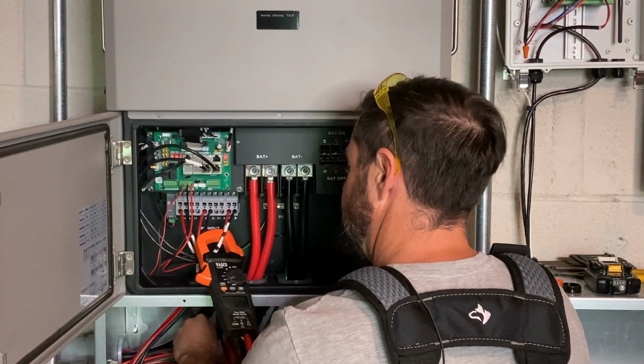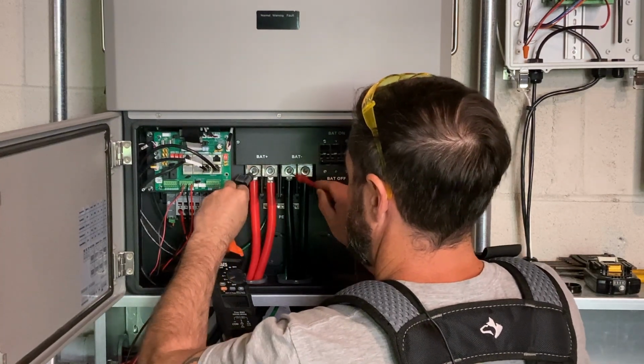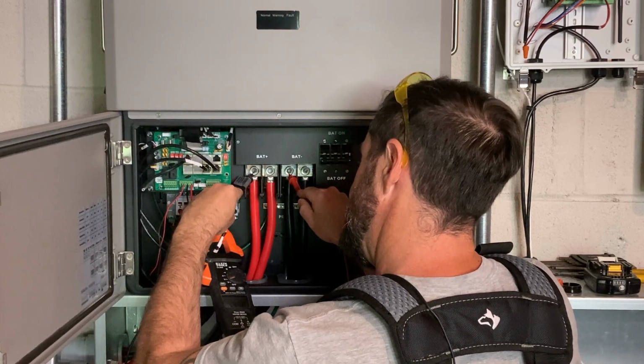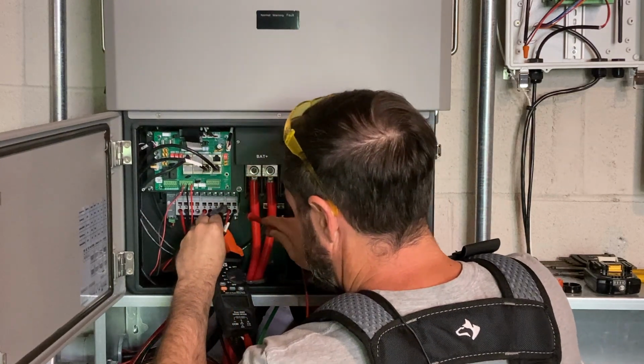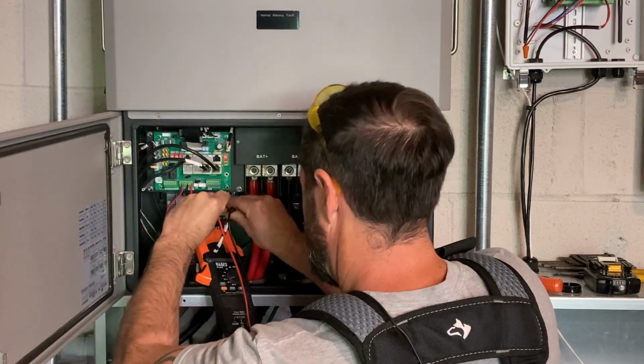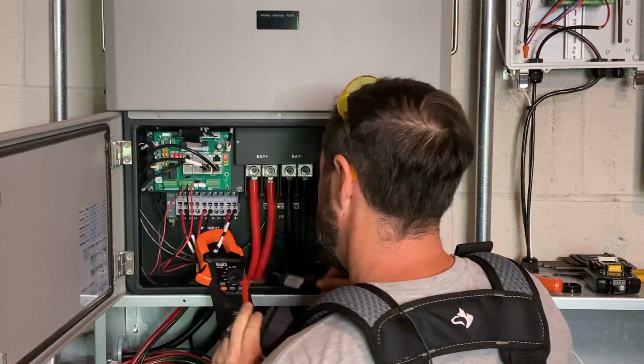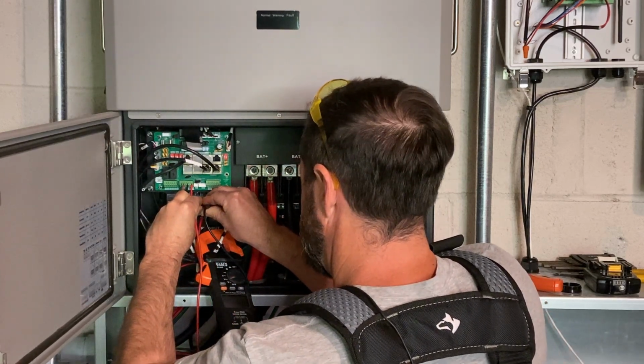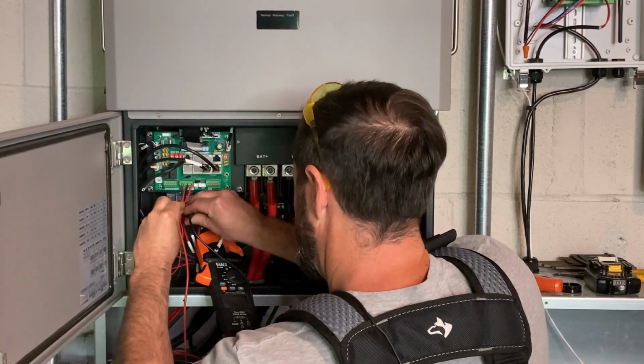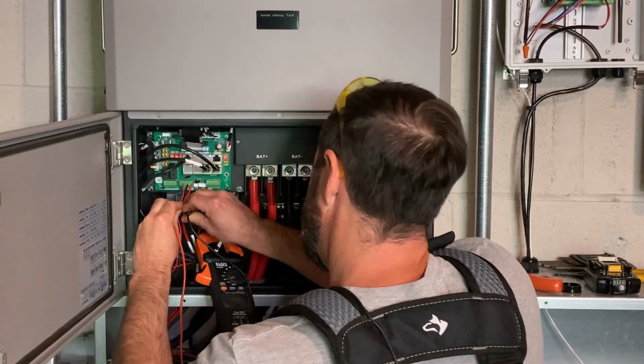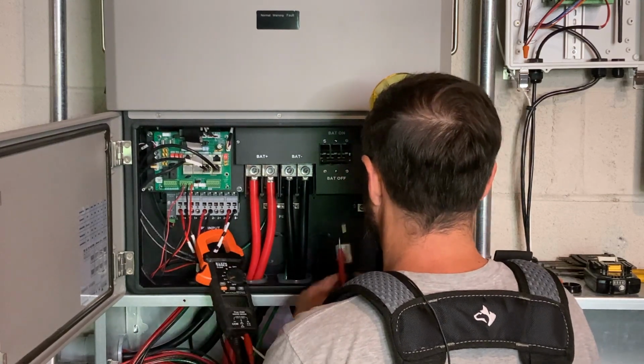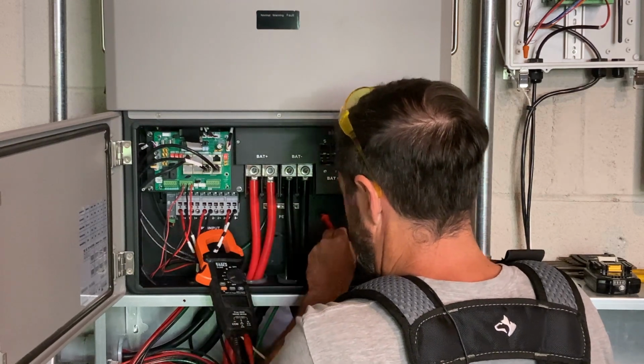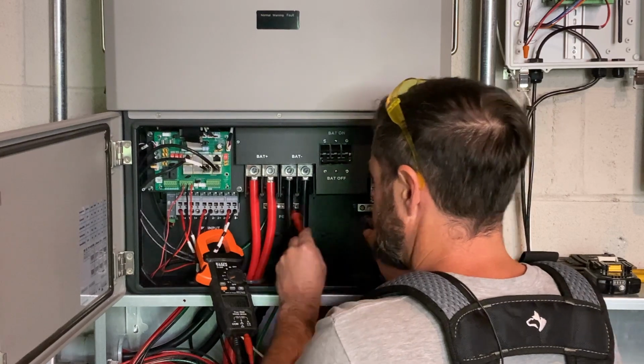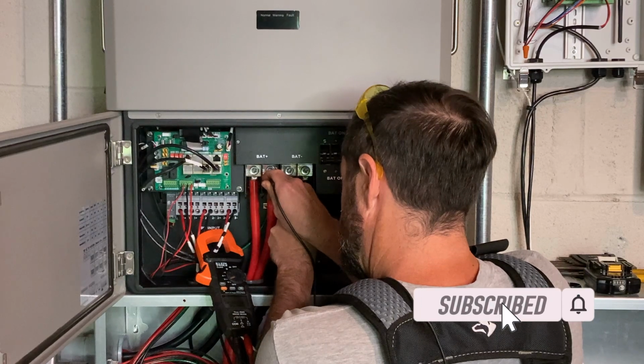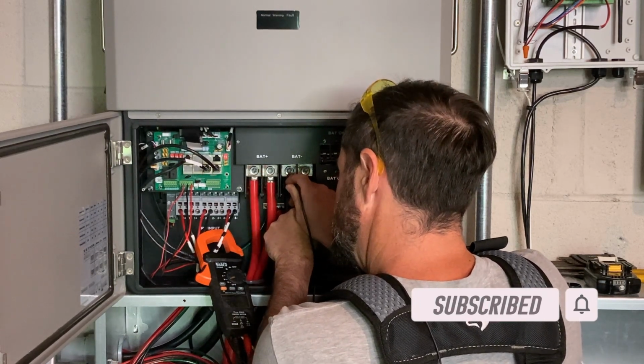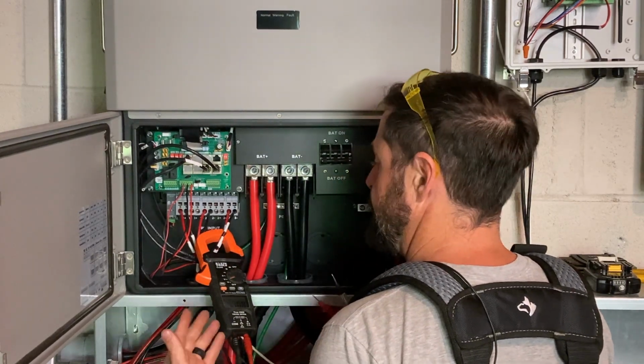I got 12 millivolts, which is essentially nothing. We're going to check our battery terminals up here, I've got 45 millivolts. We're going to check our PV conductors, I got 0 volts. We're going to check all of our MPPTs, 0 volts. This one's got 12 millivolts. Let's check ground to neutral, 0 volts. Ground to hot, 7 millivolts. Ground to negative, a few millivolts. I think it's safe to say we're good to work on this.